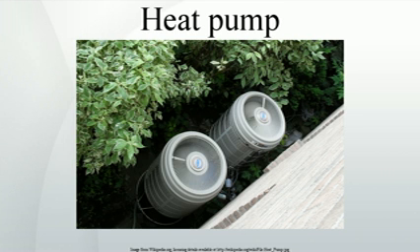Coefficient of performance, COP, and lift. The COP increases as the temperature difference, or lift, decreases between heat source and destination. The COP can be maximized at design time by choosing a heating system requiring only a low final water temperature, for example underfloor heating, and by choosing a heat source with a high average temperature, for example the ground. Domestic hot water, DHW, and conventional heating radiators require high water temperatures, reducing the COP that can be attained, and affecting the choice of heat pump technology.